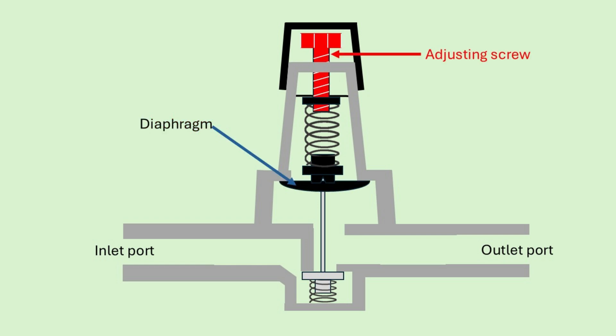Above the diaphragm is the adjusting screw. Turning the screw compresses or loosens the spring beneath it. The tighter the spring, the more force it exerts on the diaphragm, increasing the pressure required to move the diaphragm and close the valve.